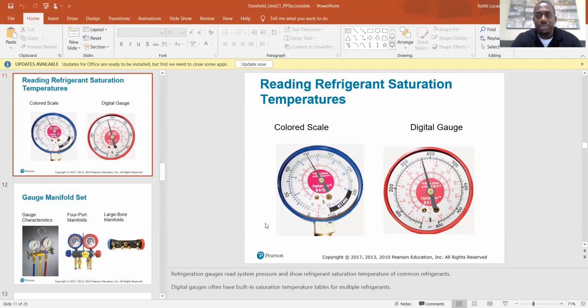So, reading refrigerant saturation temperatures. Refrigeration gauges read system pressure and show refrigerant saturation temperature of common refrigerants. Digital gauges often have built-in saturation temperature tables for multiple refrigerants. Again, digital gauges are superior. So the gauges are reading, so every refrigerant pressure has a corresponding saturation temperature.